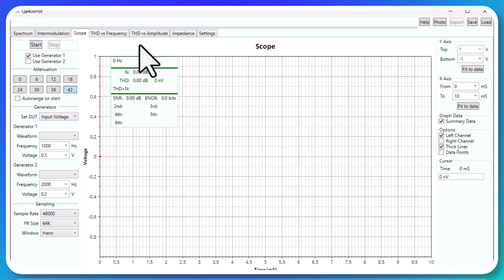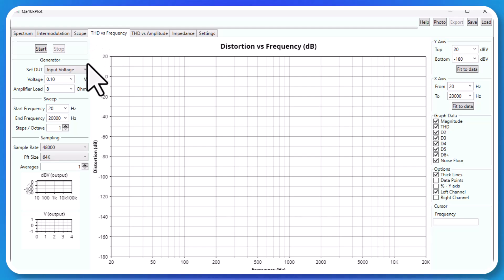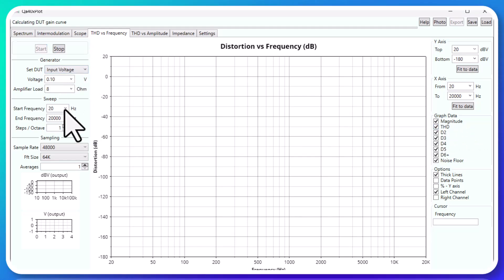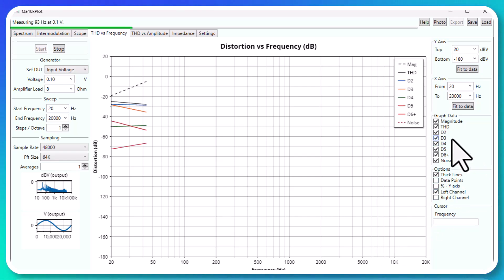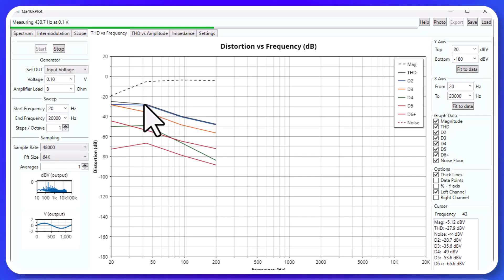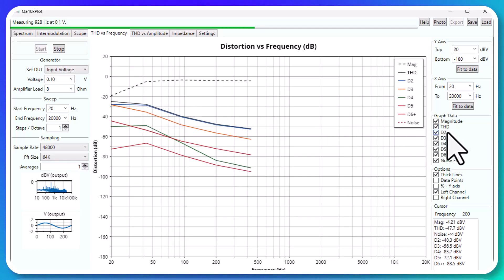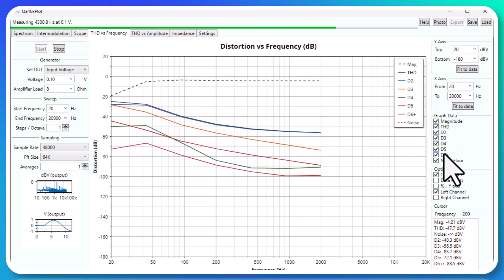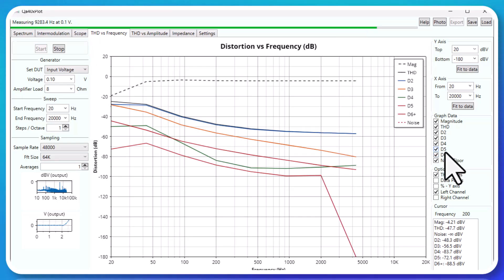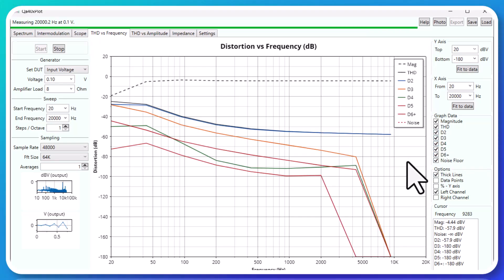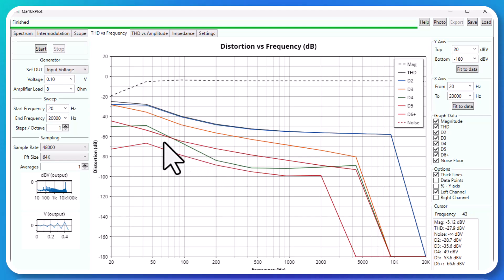You've got the ability here to do THD versus frequency. So let me kick this off and see what happens here. So what I love about it, not only do you have the primary total harmonic distortion, you've got all the individual artifacts as well here that it's measuring against.